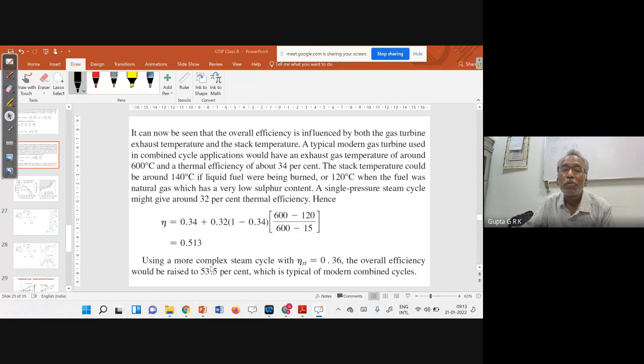And if I have a more complex steam cycle, like dual pressure steam cycle, the steam turbine efficiency will be up to 0.36. Then the overall efficiency comes to 53.5%, which is typical of modern combined cycles. Present day combined cycle power plants can have this much efficiency. It's so high actually, so that is the advantage of it.